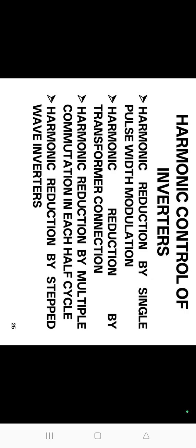These harmonics affect the operation of other equipment connected to the same system through conduction or by radio interference. The harmonics present in the inverter system lead to the following disadvantages. Harmonic currents will lead to excessive heating in induction motors connected to the thyristor system. This will reduce the load carrying capacity of the motor.